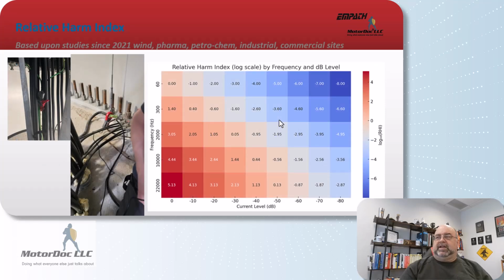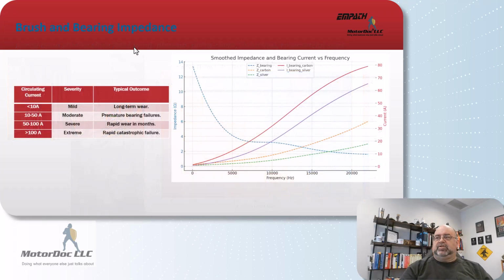So we go back again to this. There's some leads going down from the top to the yaw deck. Yaw deck is the deck immediately below the nacelle that turns, and we apply this here. This is all studies we've done since 2021. As we look at this, this is the bearing impedance coming down by frequency, and then these are a standard carbon brush and a silver carbon brush.